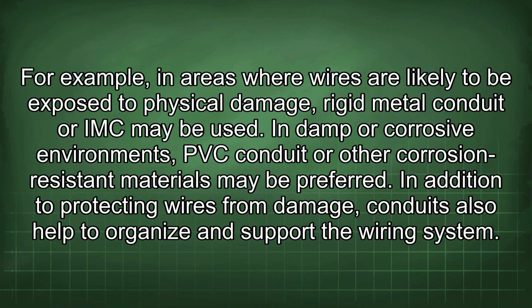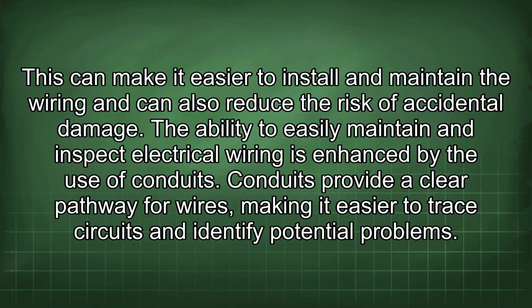The type of conduit used can be selected based on the specific hazards present in the environment. For example, in areas where wires are likely to be exposed to physical damage, rigid metal conduit or IMC may be used. In damp or corrosive environments, PVC conduit or other corrosion-resistant materials may be preferred. In addition to protecting wires from damage, conduits also help to organize and support the wiring system. This can make it easier to install and maintain the wiring and can also reduce the risk of accidental damage.